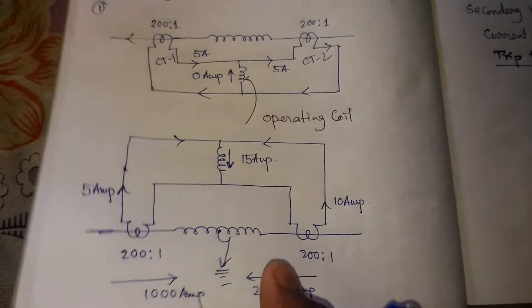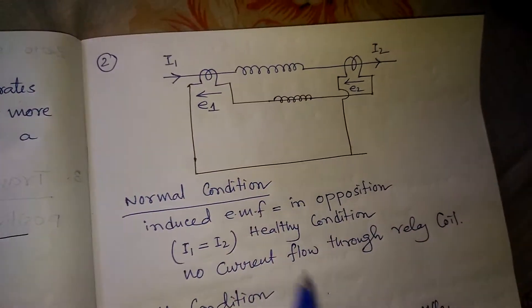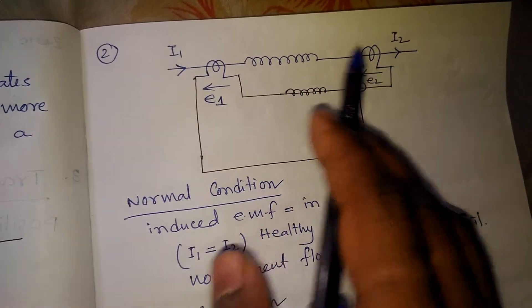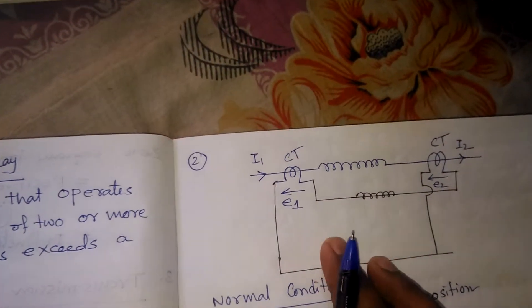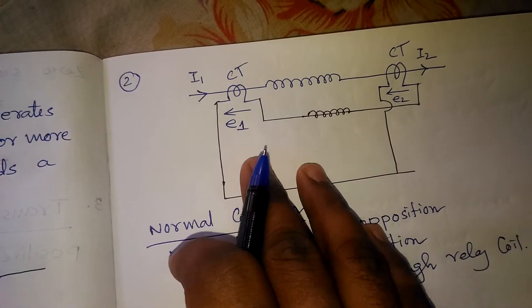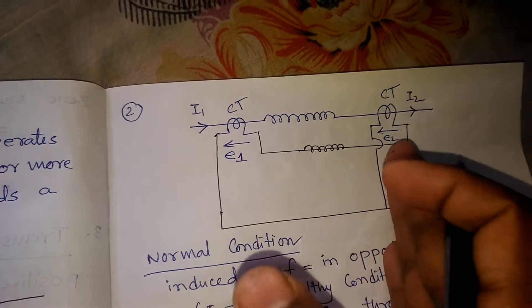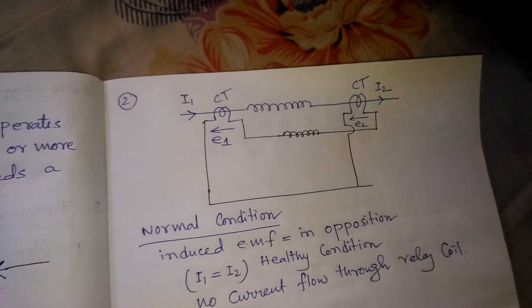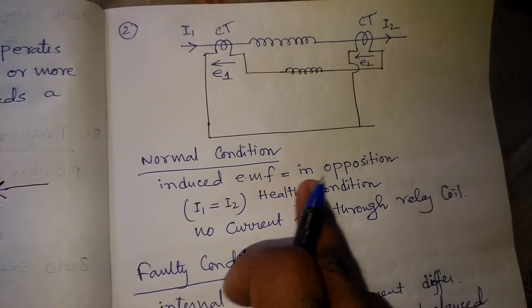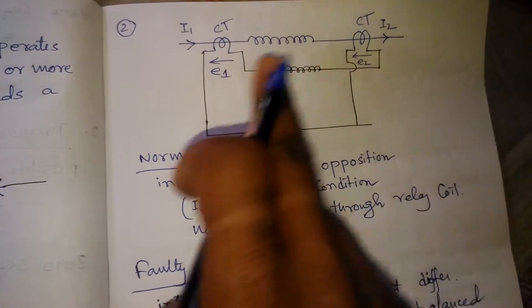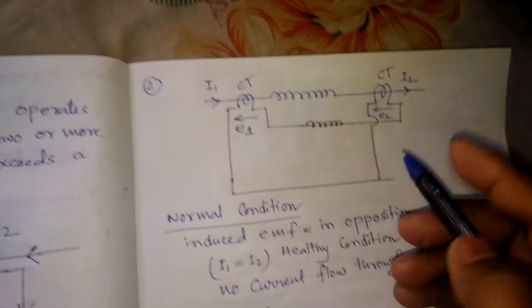The relay will operate and trip the circuit breaker. In the voltage balance protection, we use CTs on both sides and measure the induced EMF. If the induced EMF is equal to each other, in normal condition the induced EMF is in opposition: E1 equals E2, I1 equals I2 — healthy condition. So no current will flow through the relay coil.